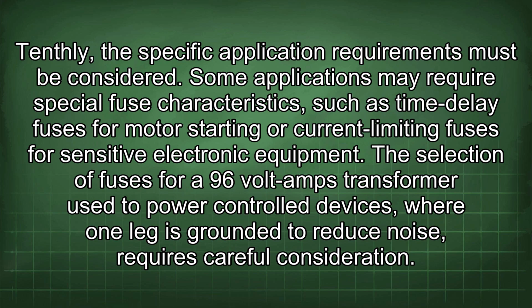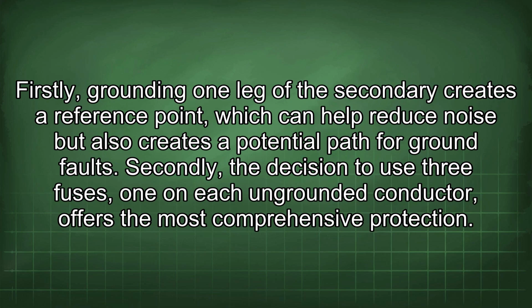The selection of fuses for a 96 volt-amp transformer used to power controlled devices, where one leg is grounded to reduce noise, requires careful consideration. Firstly, grounding one leg of the secondary creates a reference point, which can help reduce noise but also creates a potential path for ground faults.